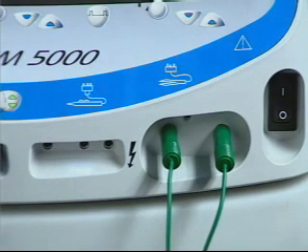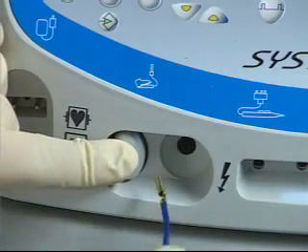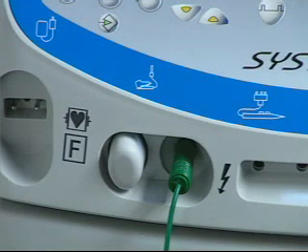The System 5000 is designed to accept both plug and lead-type bipolar cable connectors. Foot switching accessories are especially quick and simple with the proprietary ReadyPlug Universal Accessory Portal, which accepts all size single wire connectors without the need for cumbersome adapters. To use the ReadyPlug Portal, simply push in the plug release button, insert the pin tip or number 12 bovie plug, and release. 4mm accessories can be plugged directly without depressing the plug release button.